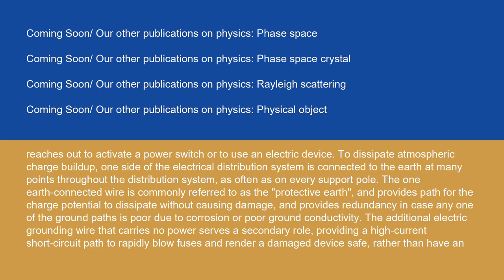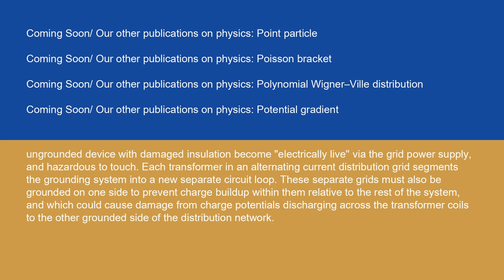The additional electric grounding wire that carries no power serves a secondary role, providing a high-current short-circuit path to rapidly blow fuses and render a damaged device safe, rather than having an ungrounded device with damaged insulation become electrically live via the grid power supply and hazardous to touch. Each transformer in an alternating current distribution grid segments the grounding system into a new separate circuit loop. These separate grids must also be grounded on one side to prevent charge buildup within them relative to the rest of the system, which could cause damage from charge potentials discharging across the transformer coils to the other grounded side of the distribution network.